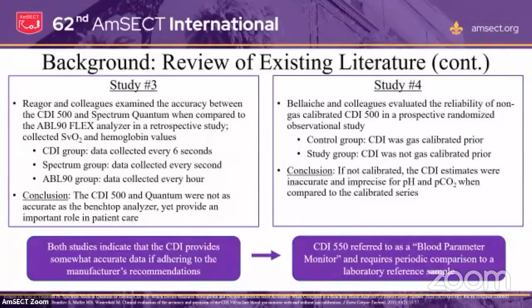So I know what's been done before. I don't know which direction to take it in, so I started reading the operator's manual, and in Appendix B, they list system accuracy limits, which can also be found in the technical compendium. And they state that the CDI has been subjected to rigorous bench tests to simulate the clinical use of the device and assess its accuracy and precision over the system operating ranges. So for example, on the right, the pH, this means that on average, the CDI read 0.007 pH units above the analyzer, or for the hemoglobin, the CDI on average read 0.17 grams per deciliter less than the analyzer.